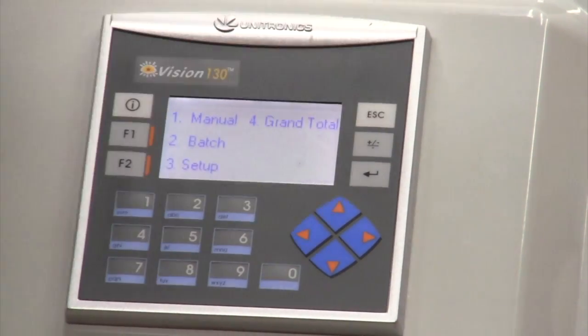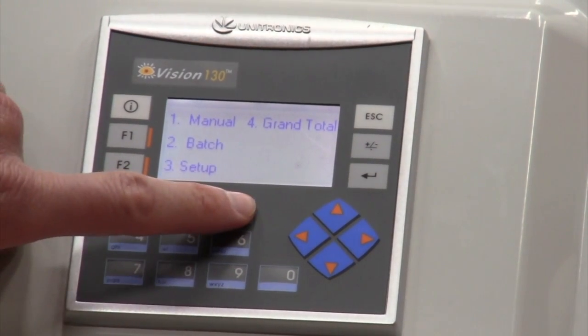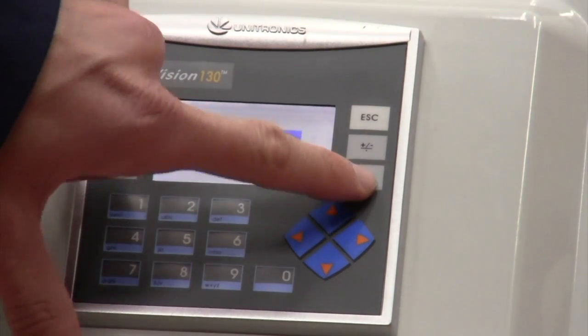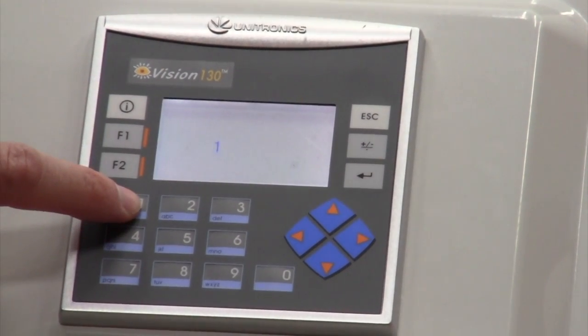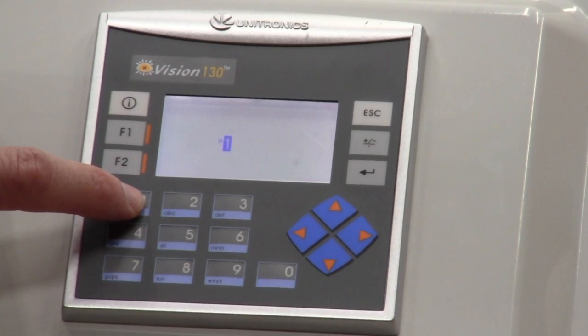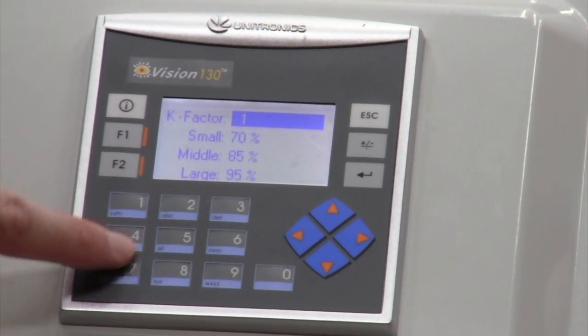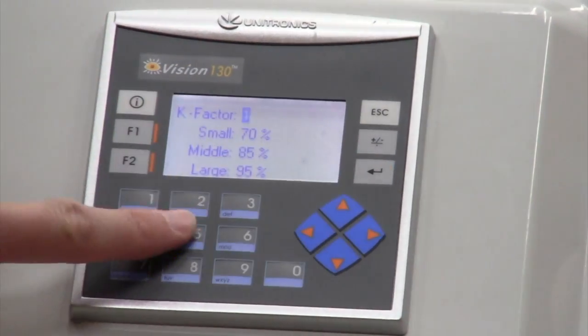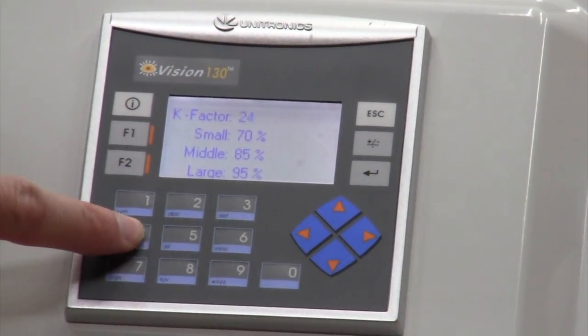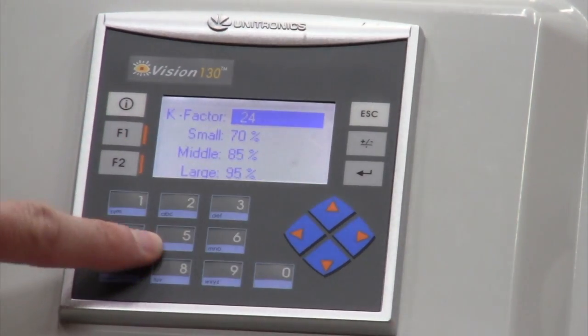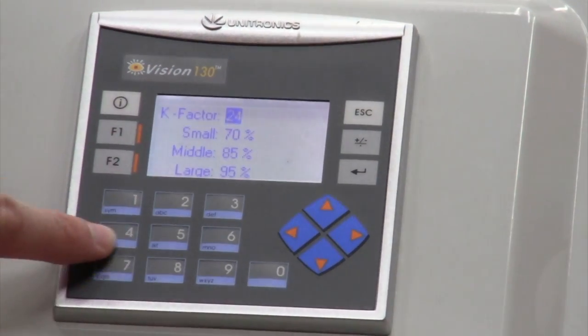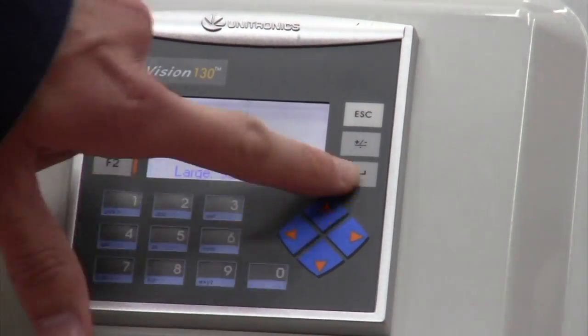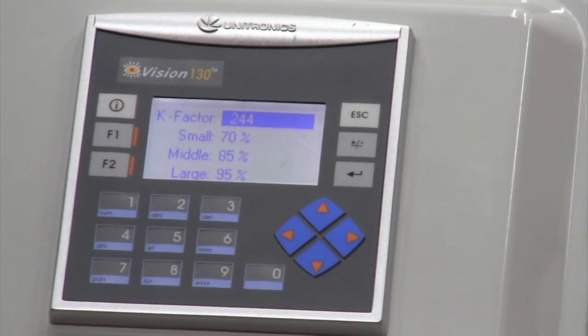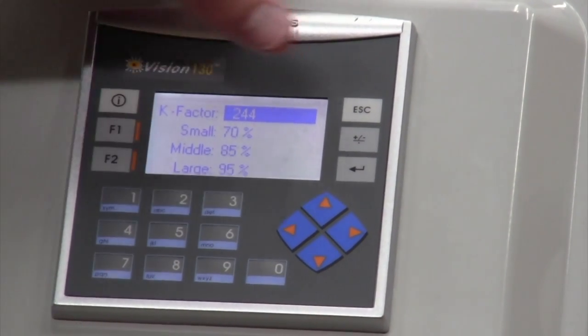Hit the escape button to get back to the main menu. Hit number 3 to go into setup. Hit enter. Type in my password of 111. And now I can change my K factor to 244. Hit enter. Now our K factor is programmed in. This meter should be calibrated.